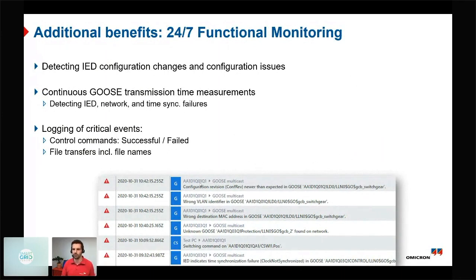An additional benefit of this detailed verification is that you also keep track of other problems. You will detect configuration issues, maybe malicious, an attack, or maybe just a mistake where somebody put a wrong configuration into a device. Such an IDS can also monitor the GOOSE transmission time continuously to detect if it exceeds a certain threshold, and it can also detect time synchronization failures, which is especially crucial in a digital substation.